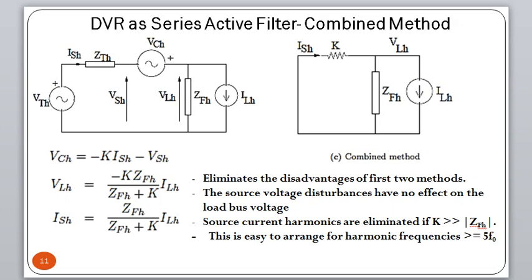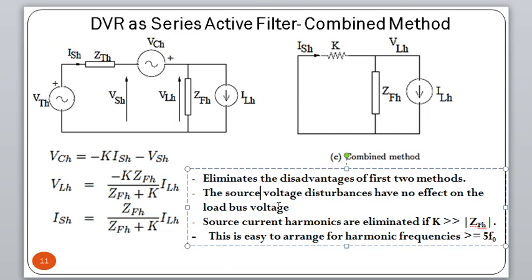In the combined method (SAF control strategy 3), the disadvantages of both previous strategies are eliminated. Source voltage disturbances have no effect on the load bus voltage, and source current harmonics ILH are also eliminated when K is greater than ZFH. This is applicable for filtering all harmonics with frequencies greater than or equal to 5F0.